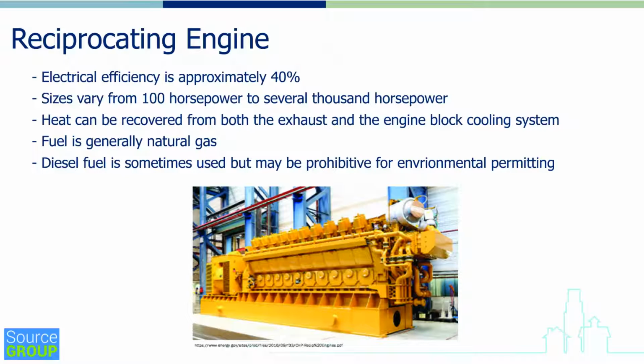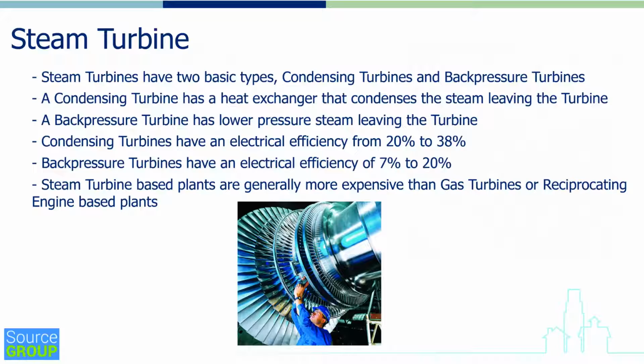The fuel used is generally natural gas. Diesel fuel can sometimes be used, but it may be prohibitive for environmental permitting reasons. Steam turbine. Steam turbines have two basic types, a condensing turbine and also back pressure turbines. A condensing turbine, which has a higher electrical efficiency, has a heat exchanger that condenses the steam that's leaving the turbine. A back pressure turbine, also known sometimes as a topping turbine, has lower pressure steam that leaves the turbine.